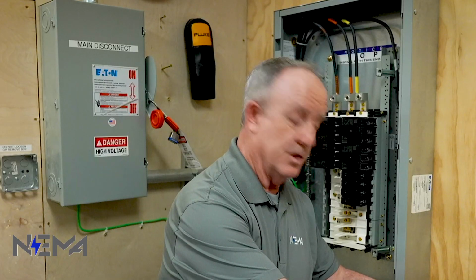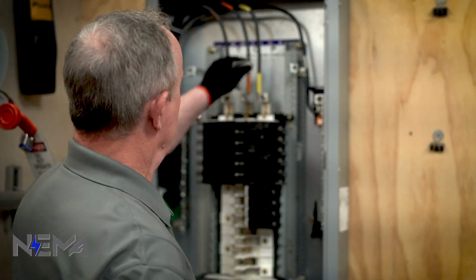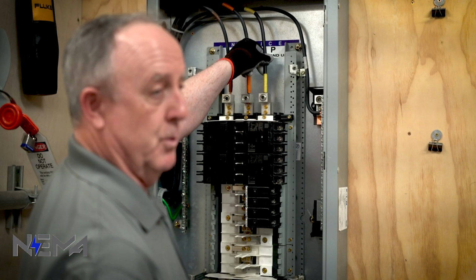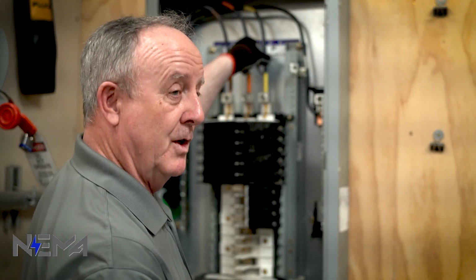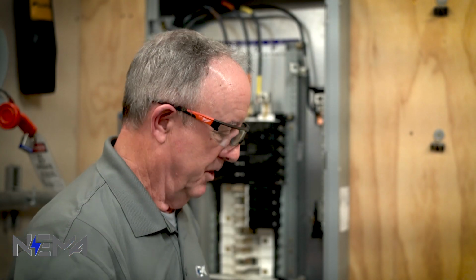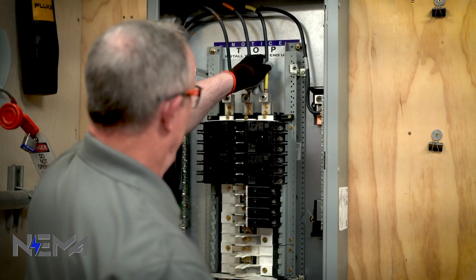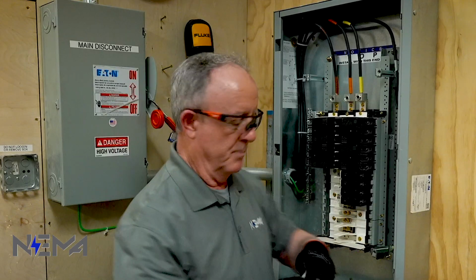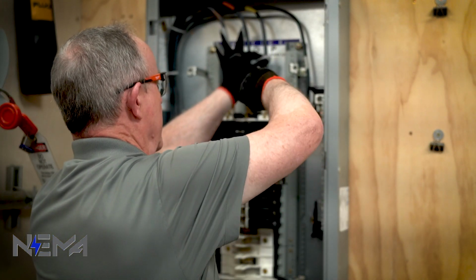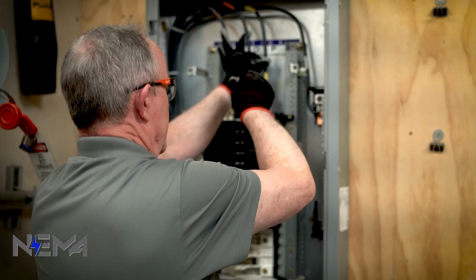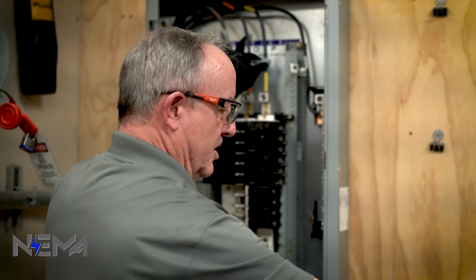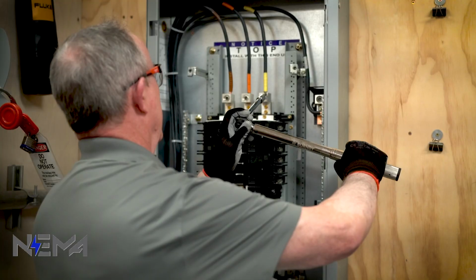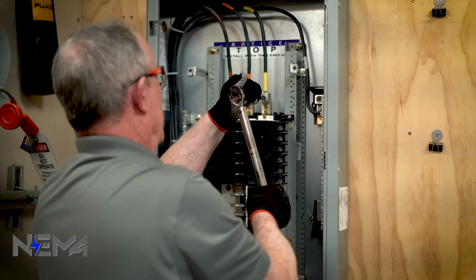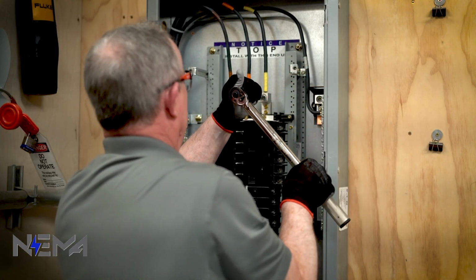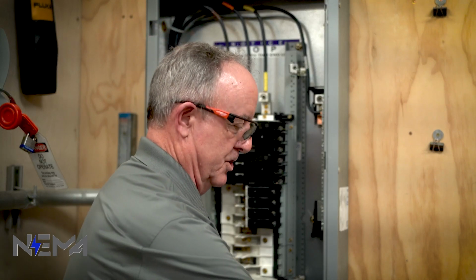So again, check the marked torque value on your equipment. You set the torque wrench to the correct value, and then sometimes you may want to use a manual tool to get the set screw to make contact with the conductor a little bit easier. So you want to strip and prepare the wire, and then take your conductor and put it into the connector, like so. And in our example, we're going to tighten it up a little bit by hand with an Allen wrench, until it makes contact with the conductor, and that'll make it a little bit easier to use the torque wrench that we're going to use to measure the torque value. And we'll complete the installation with this, like so, and we've set it to the proper value ahead of time, until it clicks, and then we know that we have the correct termination.